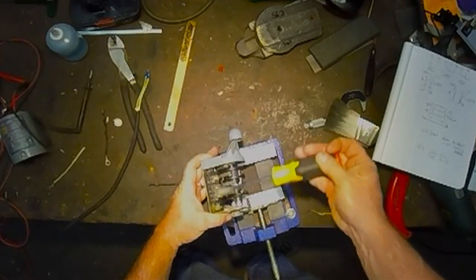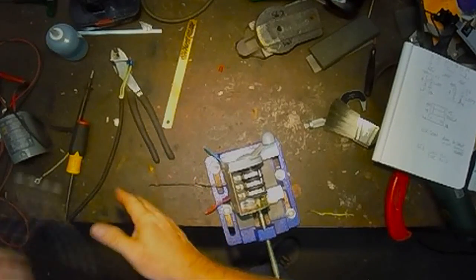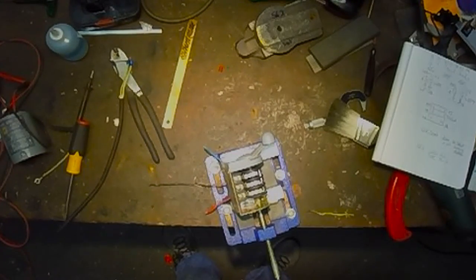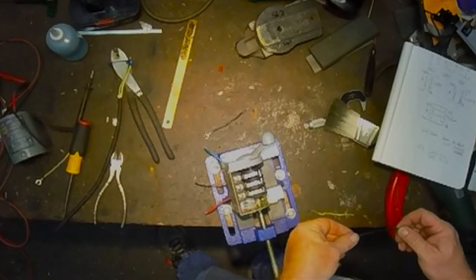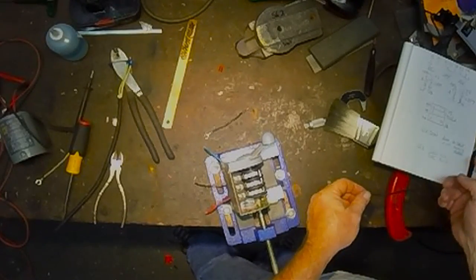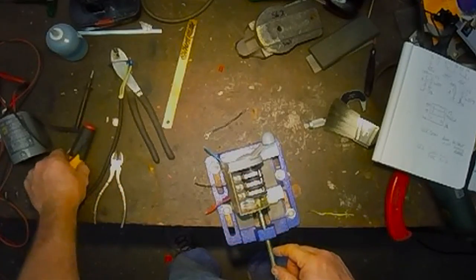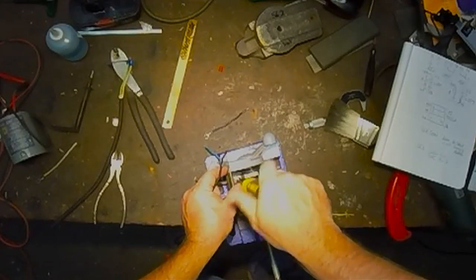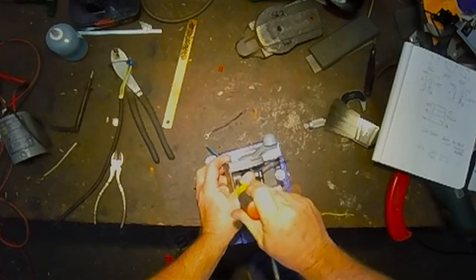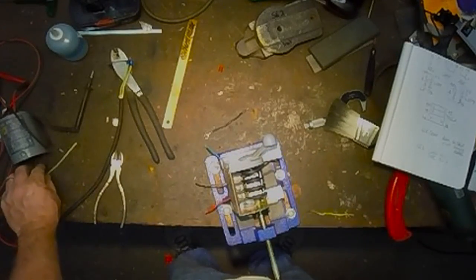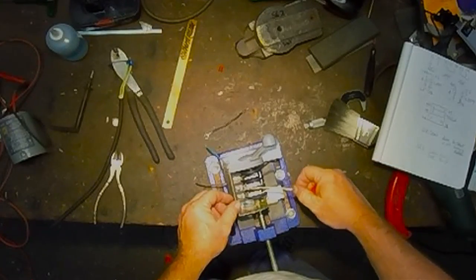Okay on this side we got one, three, and five. We're going to make a motor connection inside the motor with terminals T2 and T3. You're going to connect the wire to that and it's going to come all the way back out here to this switch and add it to switch terminal number one. And the very last motor terminal is coming from T8. T8 will connect to switch terminal number three.